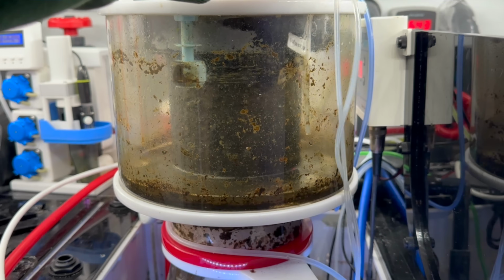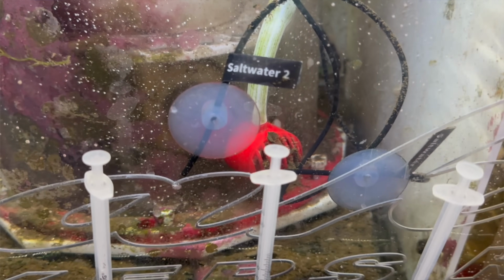But one other thing to consider is, as it does actually have two sort of test compartments in the machine, you do have two saltwater inlines and two wastewater outlines. So please do factor that in when you're looking at where you're going to mount this unit.